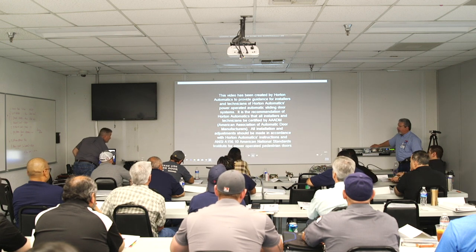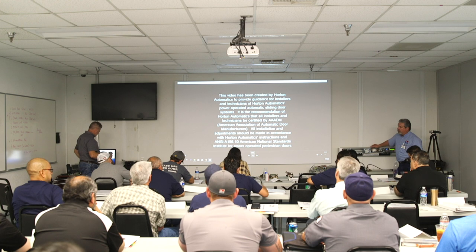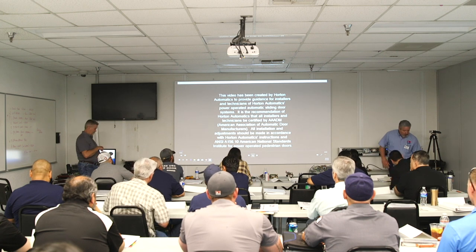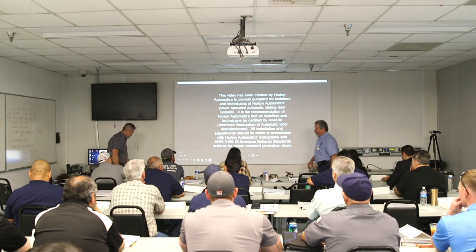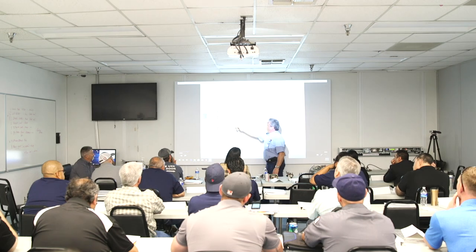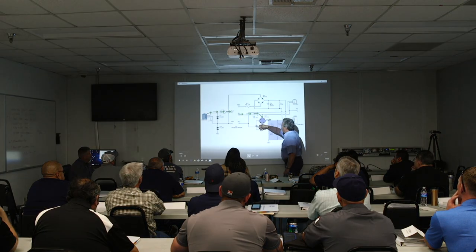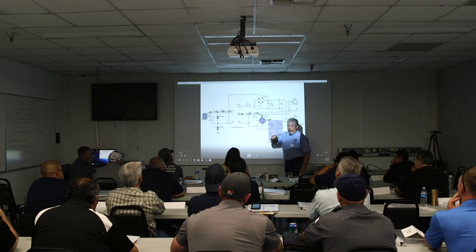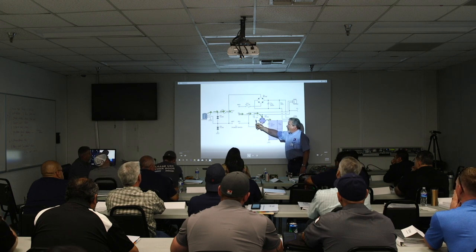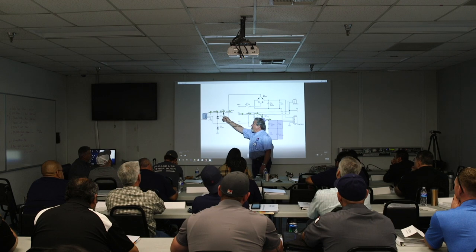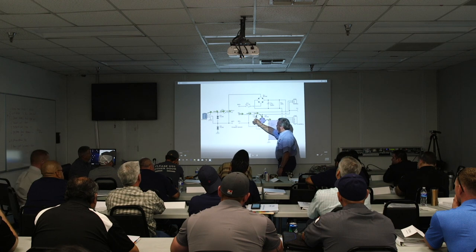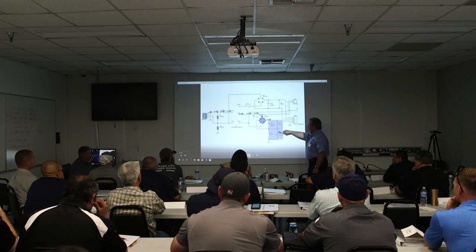AAADM, the American Association of Automatic Door Manufacturers. All installation and adjustments should be made in accordance with Horton Automatic's installation instructions and ANSI A156.10, American National Standards Institute for Power Operated Pedestrian Doors. Be sure, there are three fuses. There's F1 fuse, there's F2, and F3. They're labeled on the power supply very clearly, and they're all 3.15 amp slow blow fuses. F1 protects the incoming power supply, F2 is tied directly to the motor supply, and F3 is tied directly to the low voltage side of the control, the power that supplies power for our accessories.